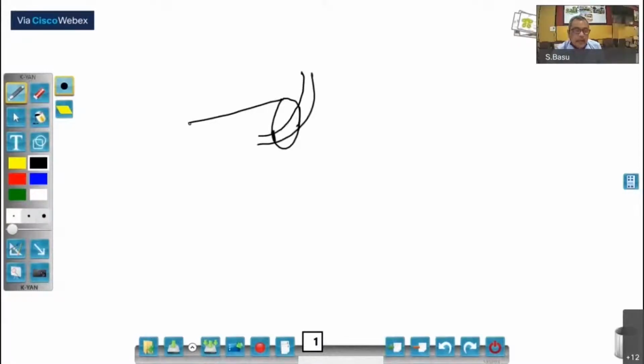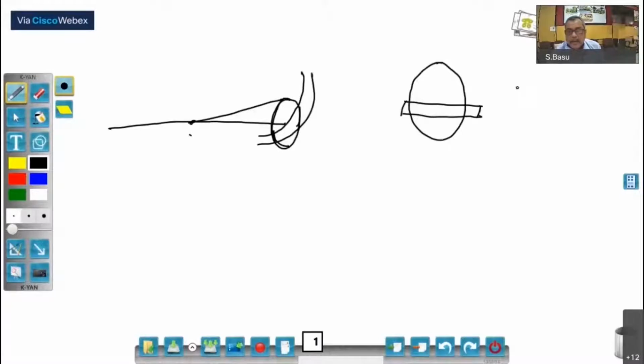So you don't need any goniometer on the sample table, because anyway you have a cone in angles around the incoming beam, around the incoming wave vector, and a part of that cone is intercepted by the detector, and you get the diffraction profile.